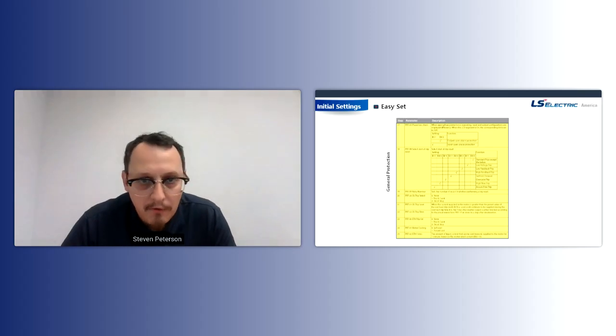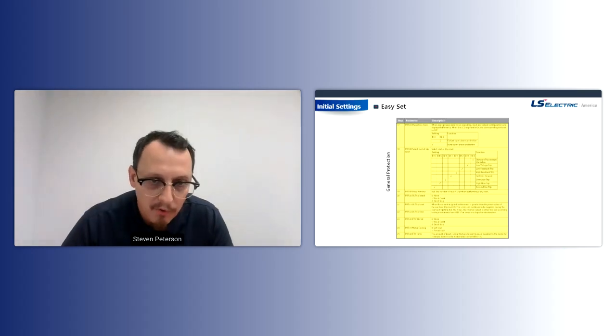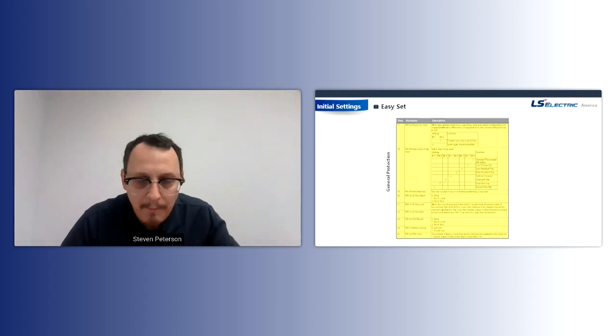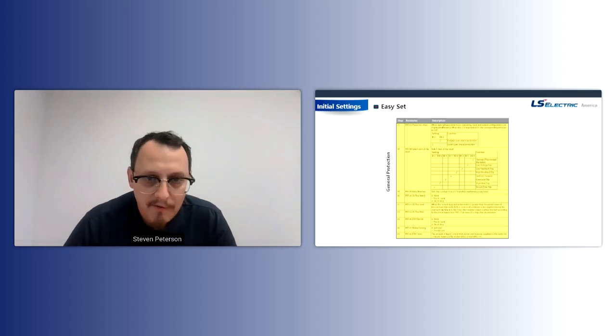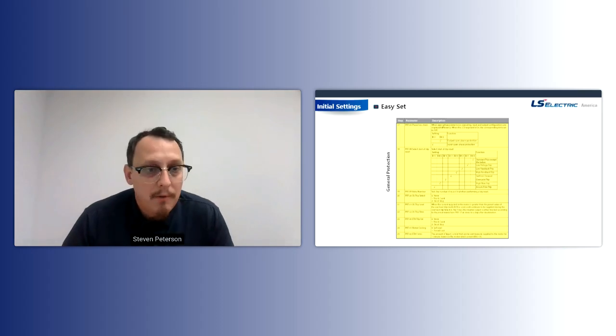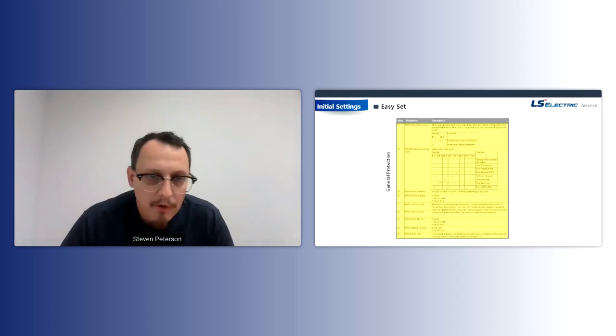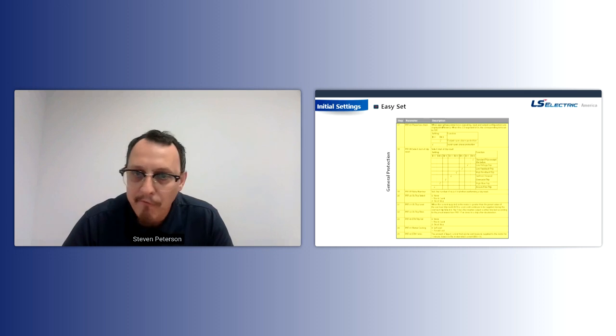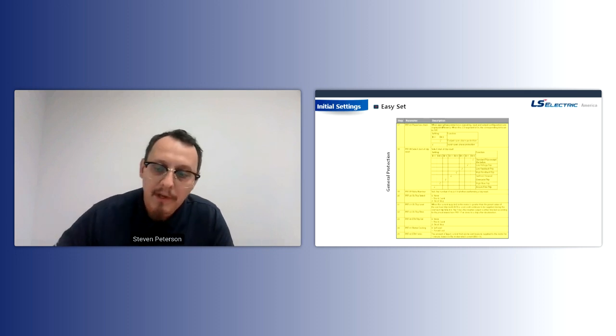You're going to enable your phase loss detection. You might set up some automatic resets and fine tune what you want to happen if the motor overloads and stuff like that. So these are general protection settings. Once you get through these 25 steps that initially pop up when the drive is powered up, you pretty much are able to run the drive. All your protection stuff is in there, you have your motor data in there, your basic control stuff. So that's what we're going to focus on now.